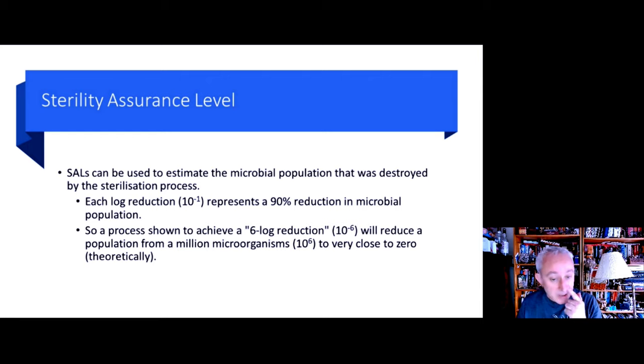And in assigning a quantitative value of a sterility assurance to say 10 to the power of minus 6, this then gives us a greater assurance of sterility than say if we were to use a SAL of 10 to the power of minus 3.